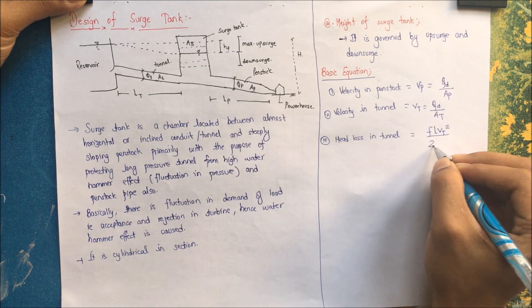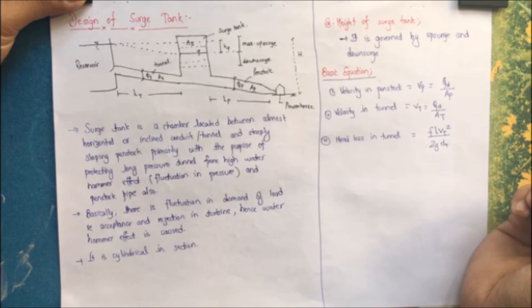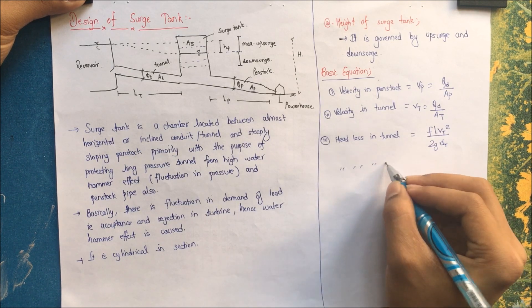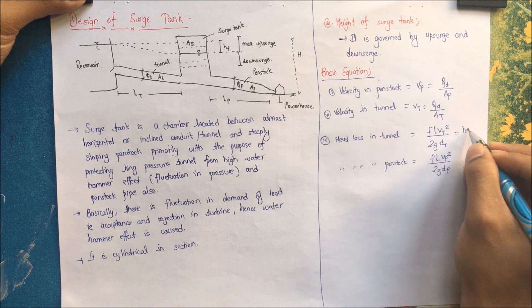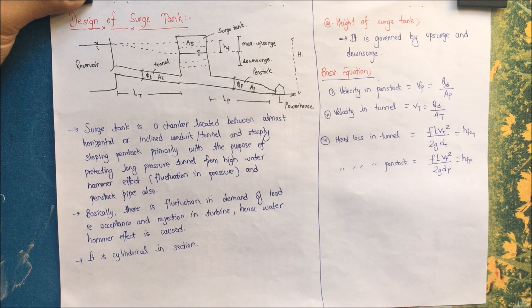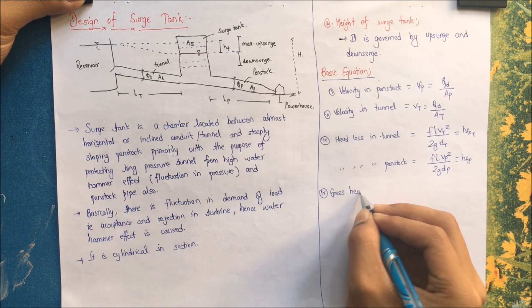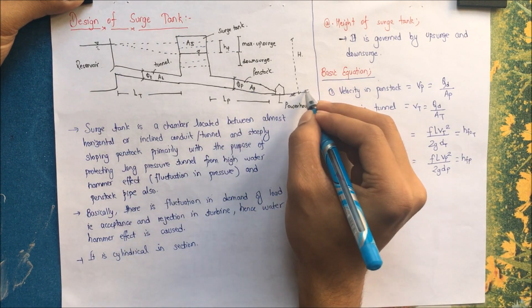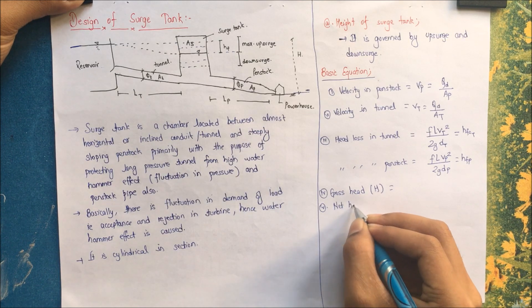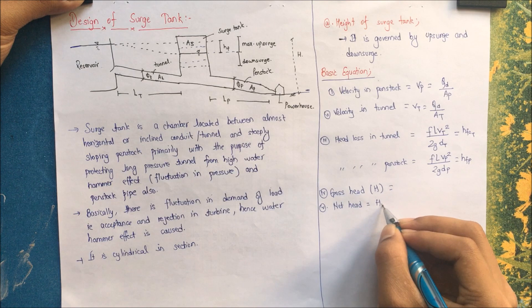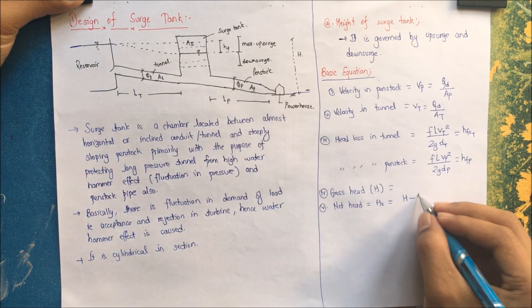Third, frictional head loss in tunnel: hft = f × L × Vt² / (2 × g × Dt), from fluid mechanics. Here f is the coefficient of friction, L is the length of conduit, Vt is the velocity in the tunnel, and Dt is the diameter of the tunnel. Similarly, head loss in penstock: hfp = f × L × Vp² / (2 × g × Dp). Step four: gross head H is the difference between the water level at the reservoir and the tailrace. Net head H₀ = H − hft − hfp.